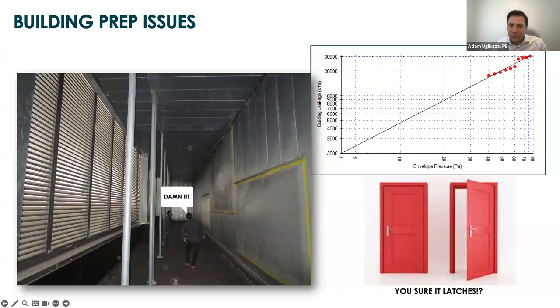So when you're watching this test, if you're concerned about passing the test, try to peek in and look at the data for the testing agency. If you're seeing something wrong with that correlation, it's usually indicating something's changed. And it's important that they go back and fix that, because that could really mean a pass or fail for the test. And that's why it's important that the testing agency is really qualified and knows what they're doing. They're going to catch things like that, correct them, start the test over, and make sure the actual CFM leakage is accurate.